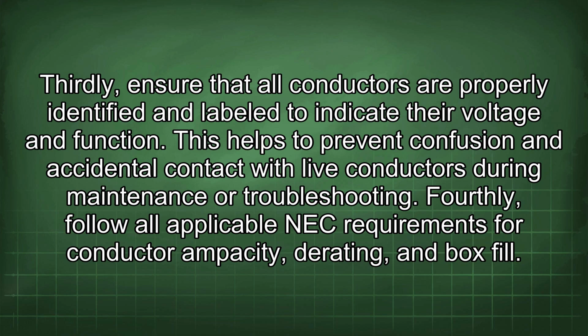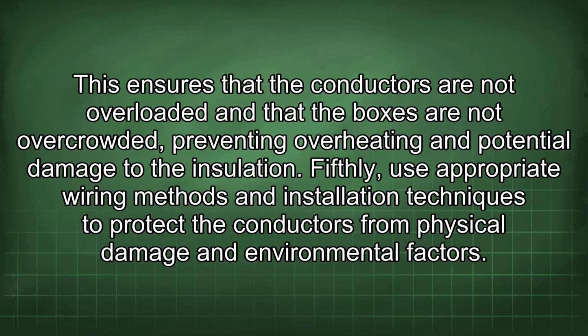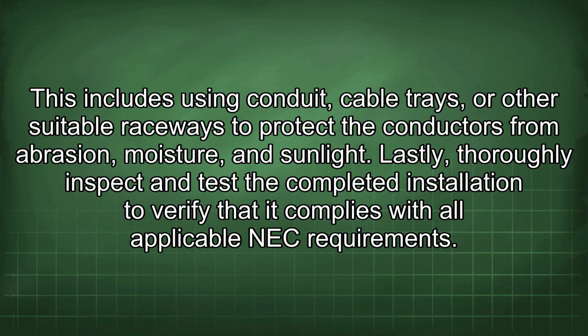Thirdly, ensure that all conductors are properly identified and labeled to indicate their voltage and function. This helps to prevent confusion and accidental contact with live conductors during maintenance or troubleshooting. Fourthly, follow all applicable NEC requirements for conductor ampacity, derating, and box fill. This ensures that the conductors are not overloaded and that the boxes are not overcrowded, preventing overheating and potential damage to the insulation. Fifthly, use appropriate wiring methods and installation techniques to protect the conductors from physical damage and environmental factors. This includes using conduit, cable trays, or other suitable raceways to protect the conductors from abrasion, moisture, and sunlight. Lastly, thoroughly inspect and test the completed installation to verify that it complies with all applicable NEC requirements.